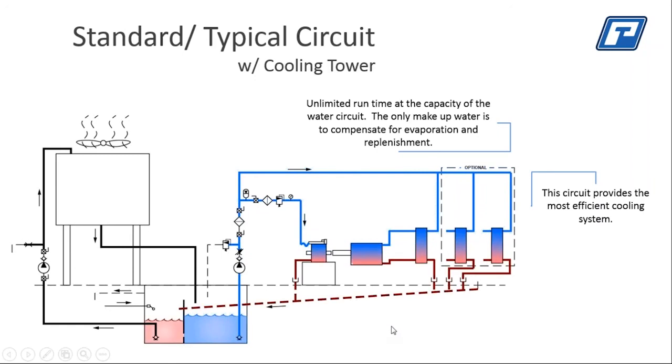Let's continue with our animation. Now we're running the system. Again, dyno engine here. We are generating load and we are generating heat that's trying to be carried off. So now you can see what's happening is the red is denoting hot. The hot water is being discharged from the 3 accessories and also discharged through the dyno. And that water is running by gravity below grade again, and it's flowing across and into the hot side. You can see it. In this case, it is not dumping into the cool side. The pipe is routed all the way across into the hot side in this illustration.